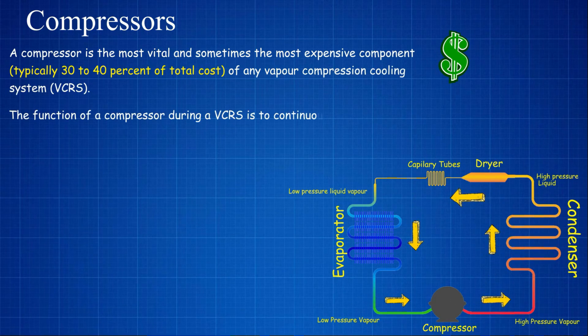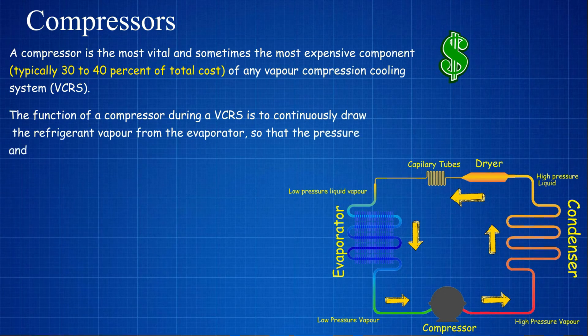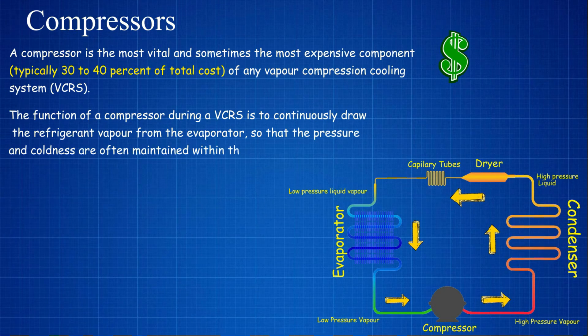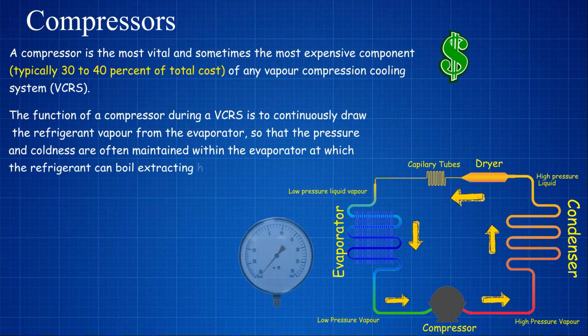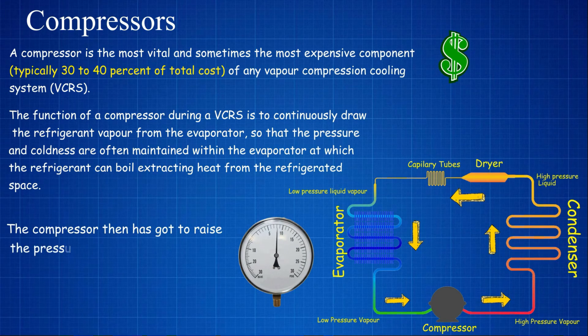The function of a compressor in a VCRS is to continuously draw the refrigerant vapor from the evaporator so that the pressure and coldness can be maintained in the evaporator at which the refrigerant can boil, extracting heat from the refrigerated space. The compressor then has to raise the pressure of the refrigerant to a level at which it can condense by rejecting heat to the cooling medium in the condenser.